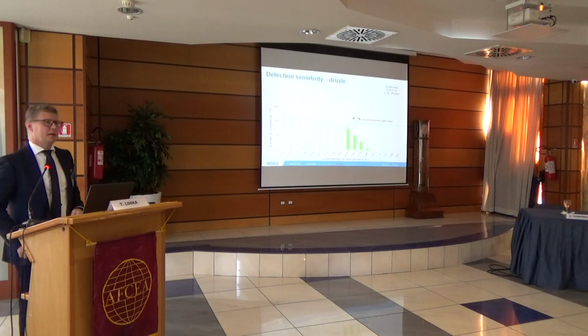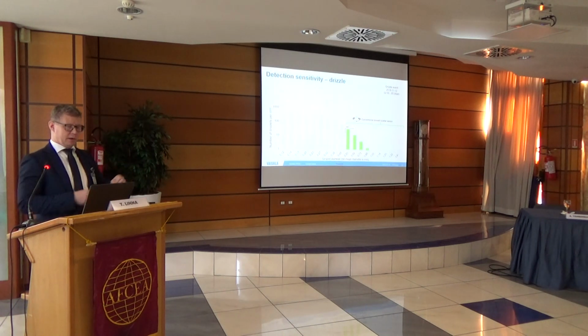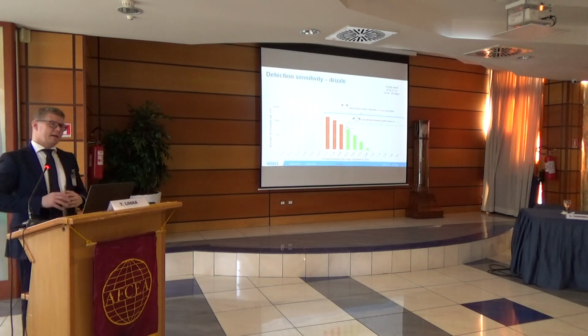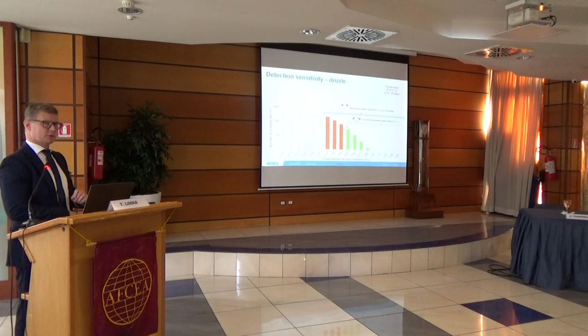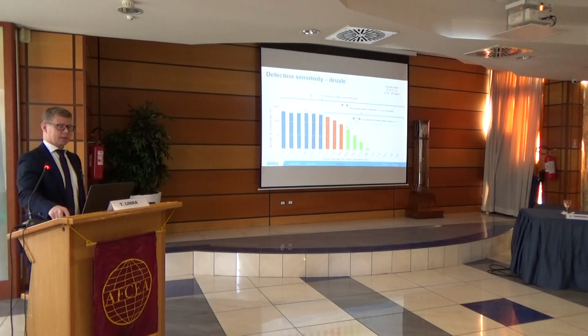And now it gets even more interesting. This is a conventional forward scatter sensor with a light cone transmitter and conventional receiver. It can only see rain in reality. So it's blind to the smaller particles, like drizzle particles. If we enhance the system and add a conventional optical light sheet based disdrometer, here in orange, it can see down to the drizzle category. However, it struggles seeing particles smaller than 0.3 millimeters. So it is completely blind to those particles. Then we add the FD70, which sees beyond, down to smaller than what is even supposed to be reported as precipitation.